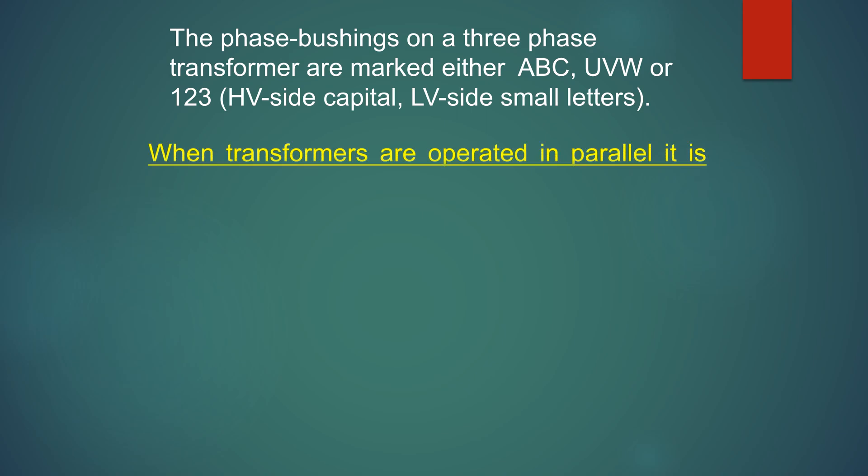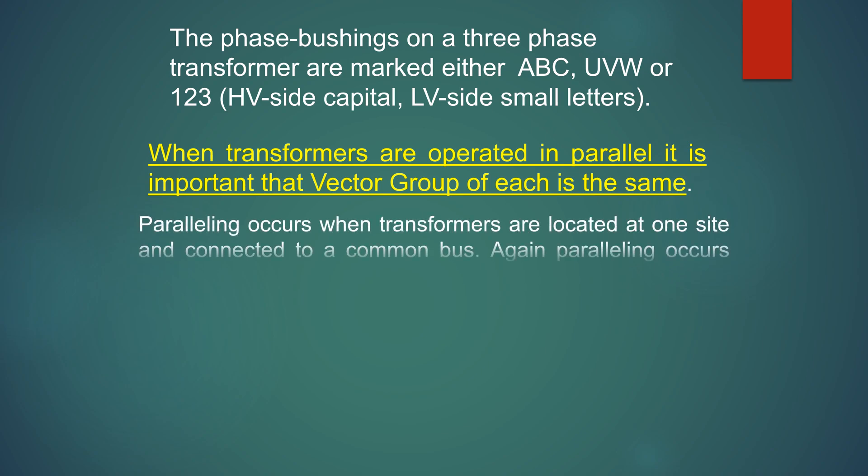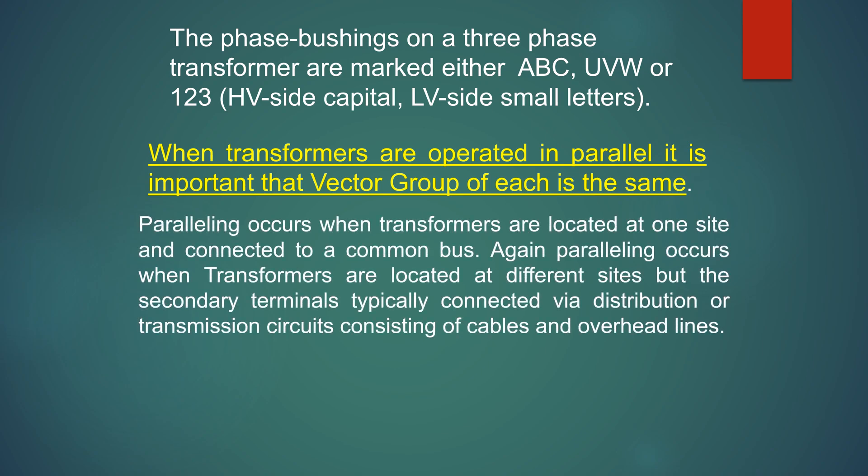When transformers are operated in parallel, it is important that the vector group of each is the same. Paralleling occurs when transformers are located at one site and connected to a common bus, or when transformers are located at different sites but their secondary terminals are connected via distribution or transmission circuits consisting of cables and overhead lines.